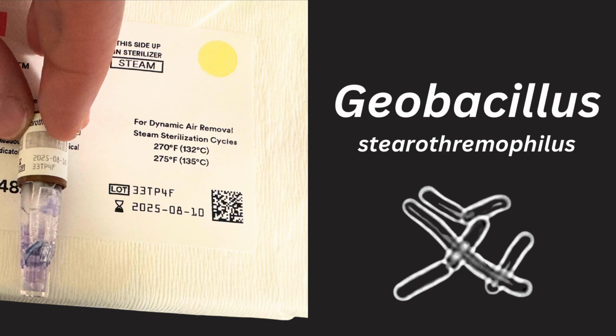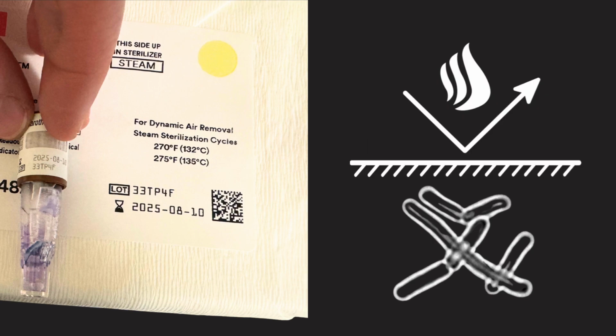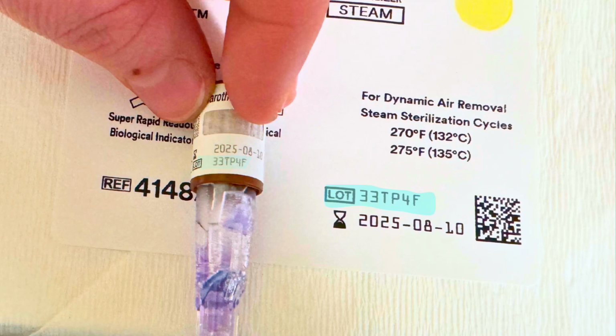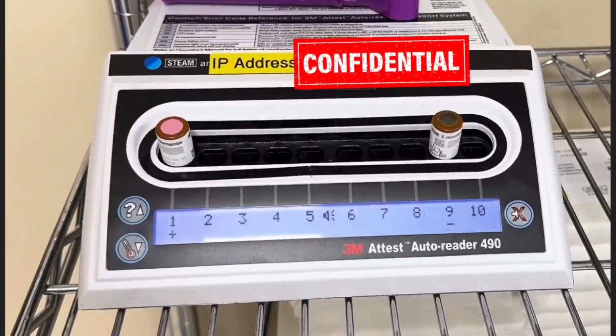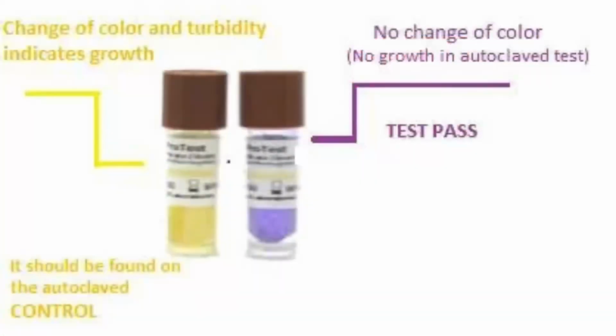Our book states the endospores of the obligate thermophilic bacterium are the gold standard used for this purpose because of their extreme heat resistance. Like any proper science experiment, a control biological with the same lot number is incubated. Our machine uses fluorescence to check and read the test. A control must alarm a positive result. It will turn yellow, allowing us to visually confirm growth, while a passing test will remain purple and negative.